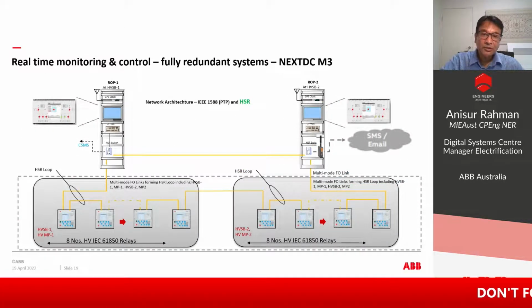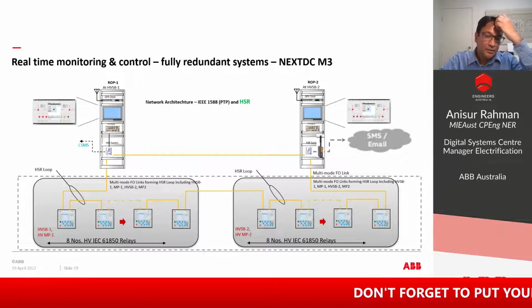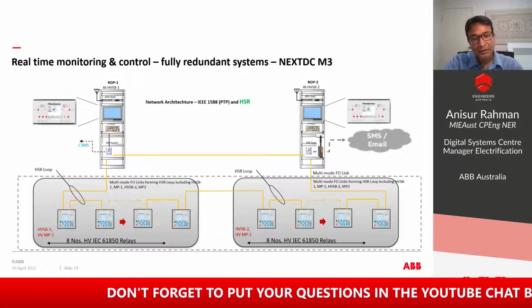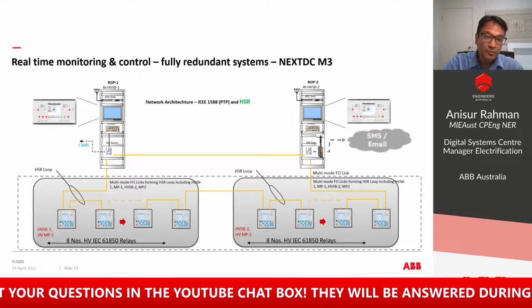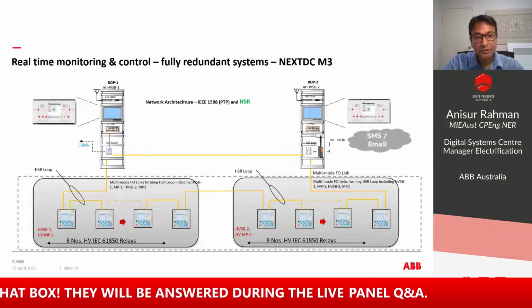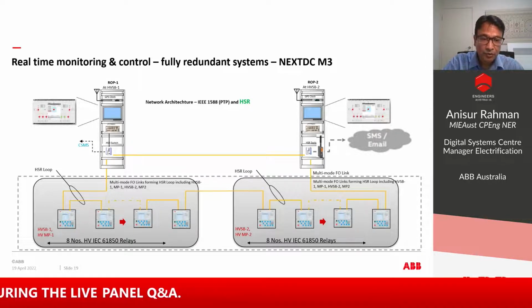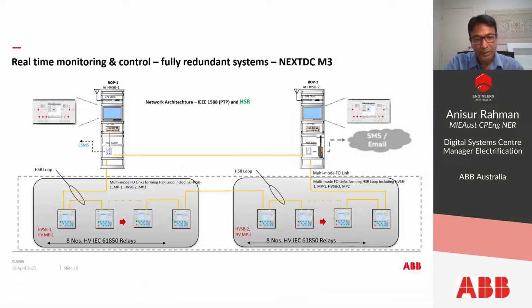This real-time monitoring and control for NextDC, we use fully redundant systems. Here we use two redundant systems with HSR loop to provide full redundancy. There is no single point of failure to stop the real-time monitoring and control, like any loop failure or port failure or any device failure, even switch failure or even panel failure. If one panel goes down, the other panel can still access the whole network.